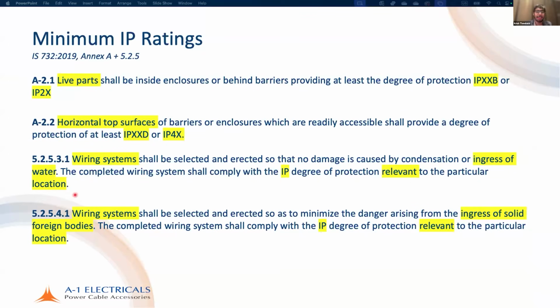So every location should be studied on a case by case basis, and I'll show you where in the standard you can figure this out. What is your particular case, and we need to figure out what is the level of IP protection required. And importantly, wiring systems shall be selected and erected so as to minimize the danger arising from the ingress of solid foreign bodies. So we don't want dust to enter, for example. The completed wiring system shall comply with the IP degree of protection relevant to the particular location. So again, this is the minimum. In a completely sterile environment, also this is required.